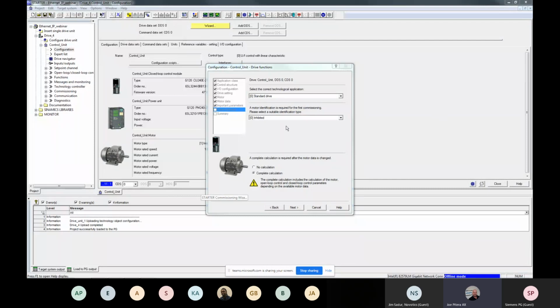We are going to say this is just a standard drive, but we want to do a motor identification to make sure that we identify the motor's magnetizing current, the resistance of the cables, and the motor inductance as well as iron core as well, to make sure the motor is identified by the drive for tuning. We are going to identify the motor at standstill. Here is the selection we're going to utilize.